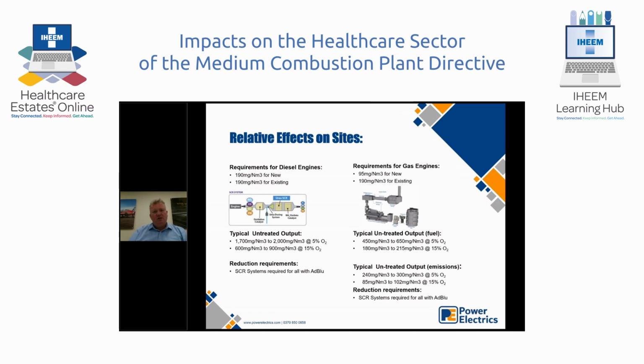With regards to gas engines, the NOx levels are lower. As I said before, this only focuses on NOx from the medium combustion plant directive. So for new, it needs to be at 95, and for existing, it needs to be at 190. Again, looking at the 15%, a gas engine will run between 180 and 215 at fuel optimized, and at emissions optimized it can run between 85 and 102. So in theory, it's possible to meet this legislation without abatement on gas engines, but effectively you will burn more fuel. One of the things you'll find with engines is that you burn more fuel to make the emissions lower.